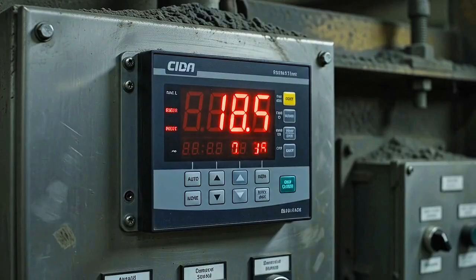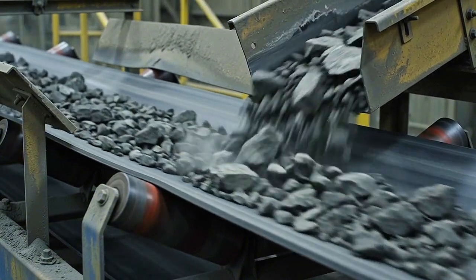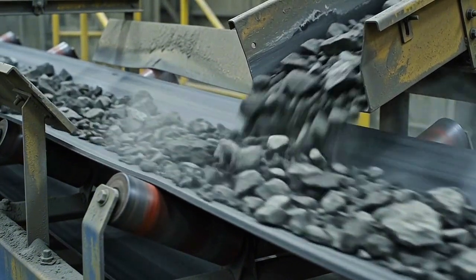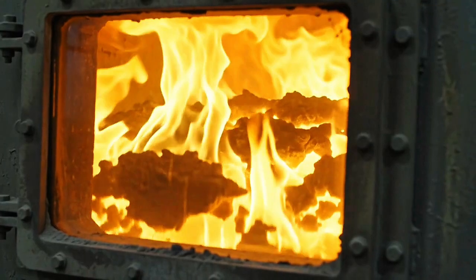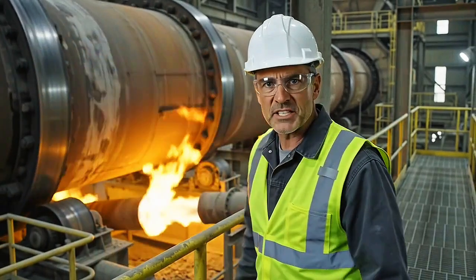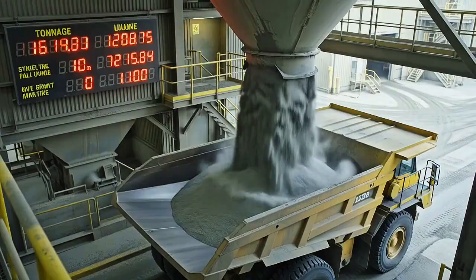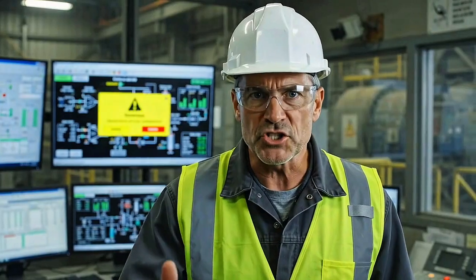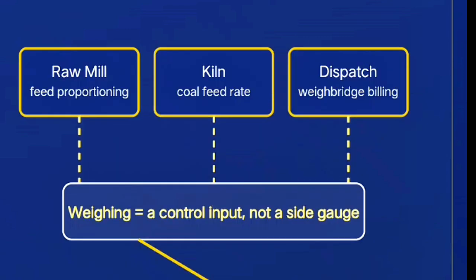In a cement plant, and this applies just as much to steel, fertilizer, food processing, any bulk material plant, weighing isn't a side instrument. It's a control input. Your raw mill feed proportioning depends on weigh feeders reading correctly, ton for ton, so your raw mix chemistry stays inside spec. Your coal feed to the kiln depends on a weigh feeder holding a stable set point, because a swing in fuel rate shows up as a swing in burning zone temperature within minutes.